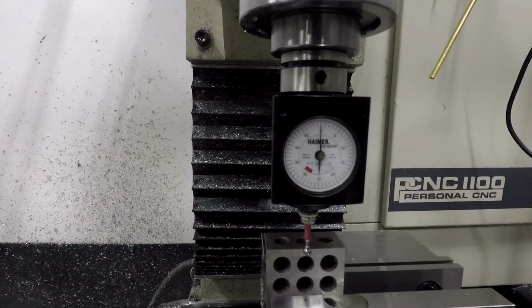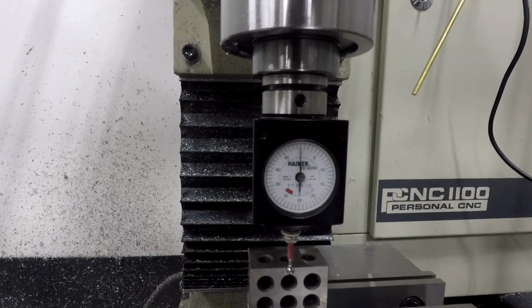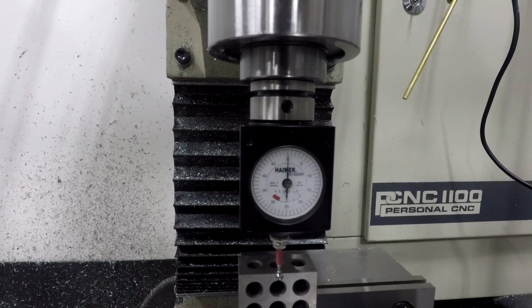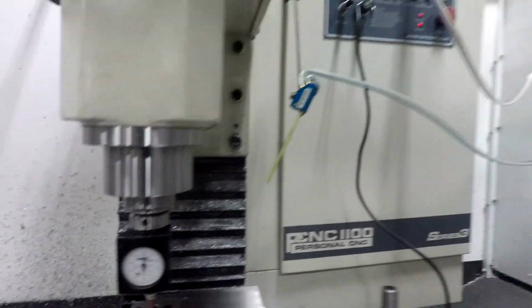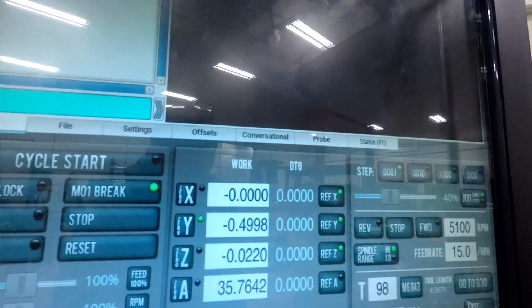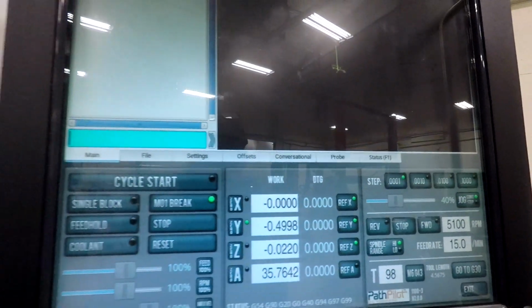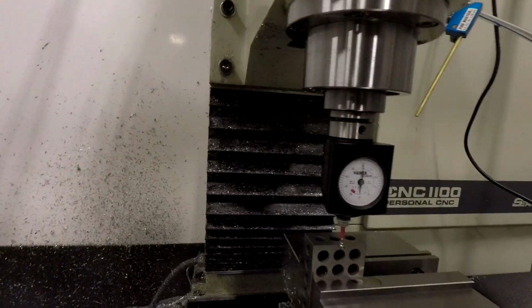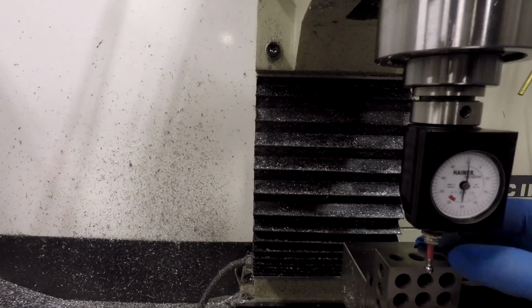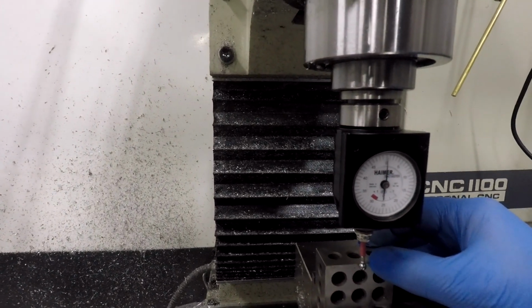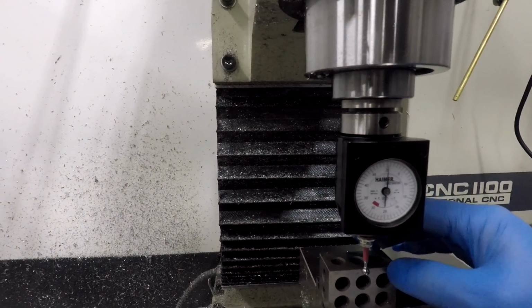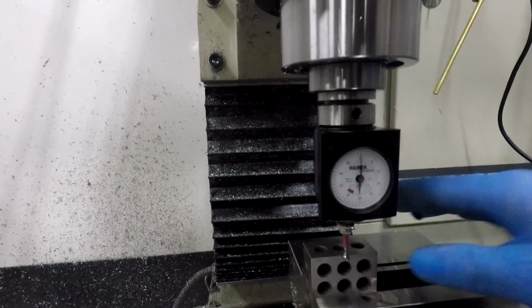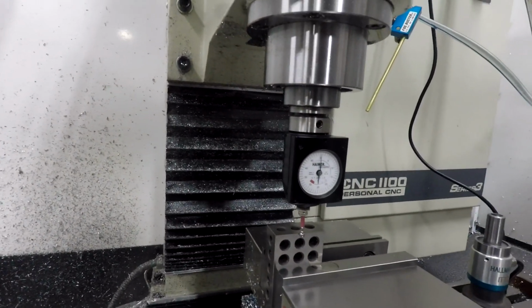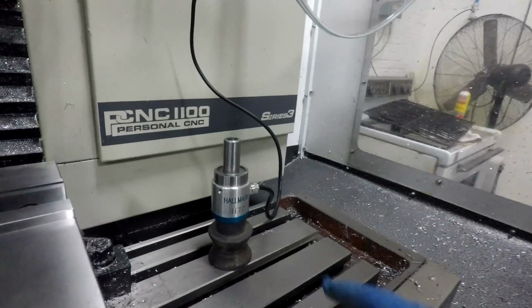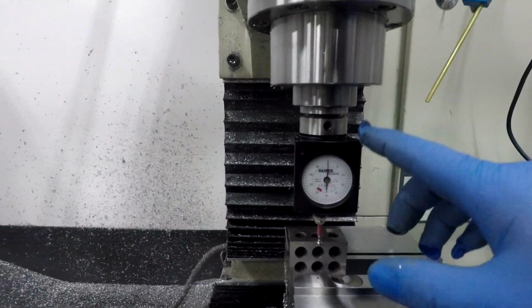But still well within tolerance. If we actually go back the other way and hit it there, we're off 2 microns. So within 1, we're 1 micron over here, 2 microns over here, which is about 1 micron off on the Y on this distance. And that could be a number of things. But still, this is way quicker to use and set up than using this.